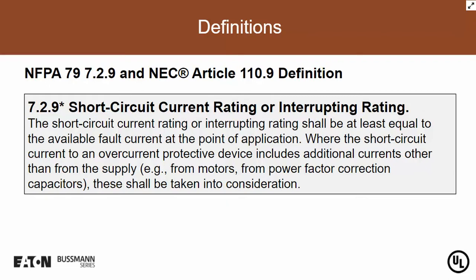Now, when we talk about short circuit current rating, it is truly an interrupting rating for active devices. And when I use the term active device, I'm talking about a circuit breaker or a fuse, because it actually can interrupt a short circuit current. So the short circuit current rating on a fuse or circuit breaker is also an interrupting rating. I recall seeing on a fuse the acronym AIC, amps interrupting current. That tells you that that particular fuse can actually interrupt current at the rating that's marked on the fuse, whether it's 100,000 amps or just 10,000 amps. It is not only a short circuit current rating, it also has an interrupting rating.